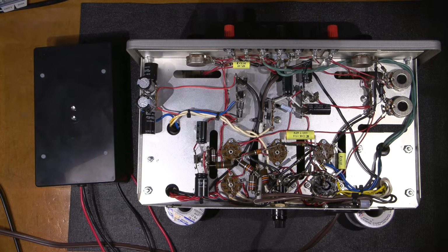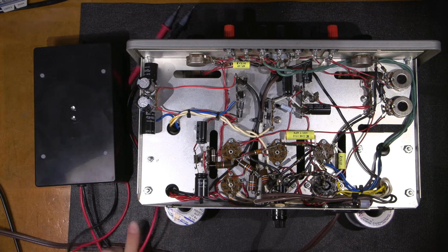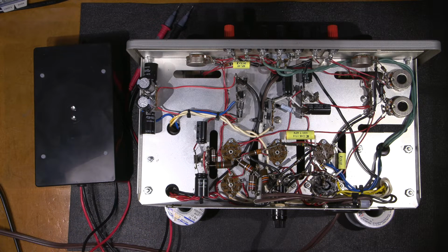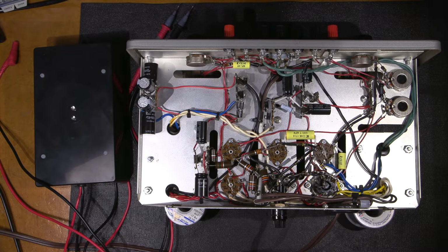So now the thing with these capacitors is there's a thing called dielectric absorption, and a lot of people don't think about this. Dielectric absorption is basically, in short, the capacitors appear to be charging back up on their own. So after a while, the capacitors that you have discharged may get up to a charge that might zap you, and you always want to make sure of that. Now, you want to make sure that you discharge these things and they stay discharged.